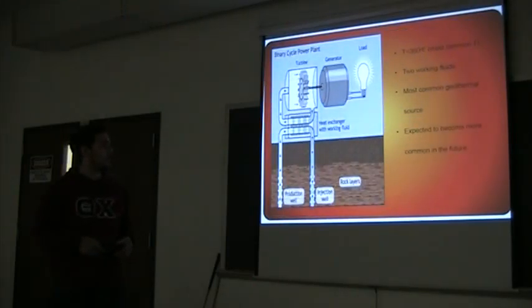A better, more modern system is for temperatures below 360 Fahrenheit. What they do is take advantage of the heat produced beneath the surface by using a second working fluid that has a lower critical point than water, so you can superheat that fluid for the turbine instead of using water which has a relatively high critical temperature.